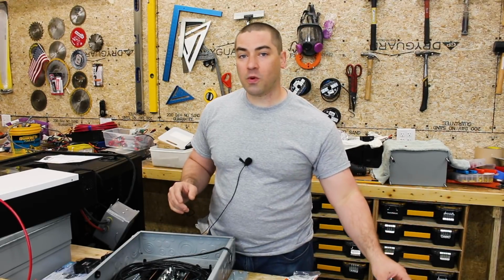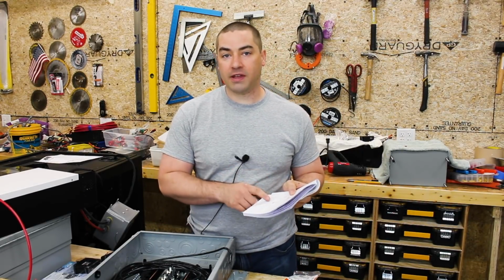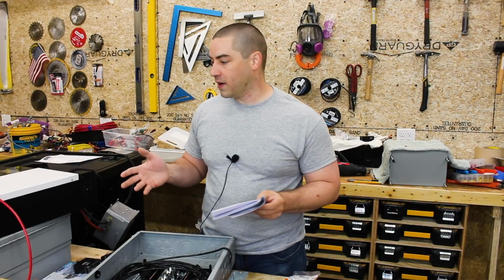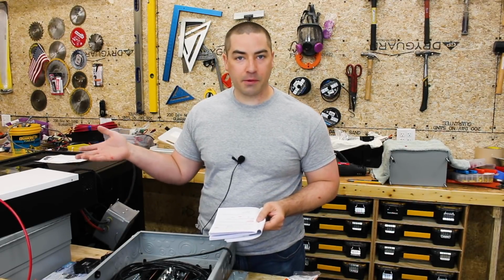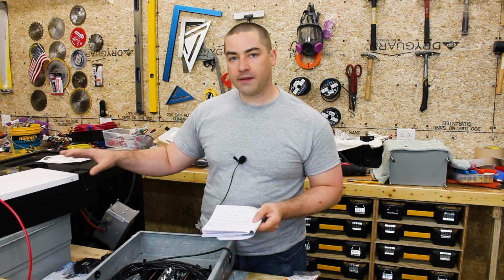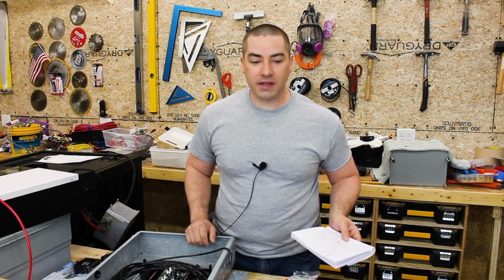Now, if anybody knows why the manual is suggesting a 50 amp breaker with 8 gauge wire, when I think a 30 amp breaker with 10 gauge wire would have sufficed, please let me know in the comments below.